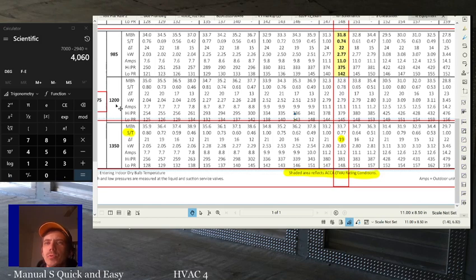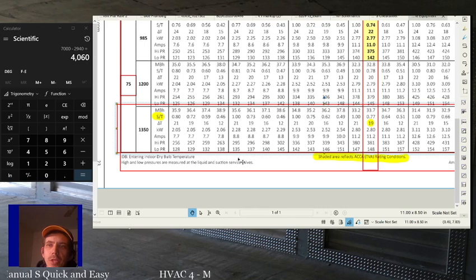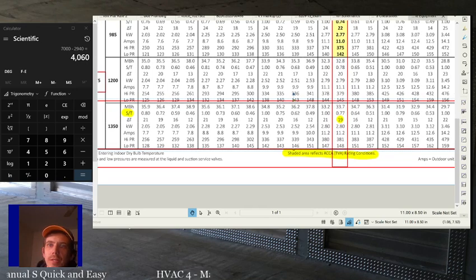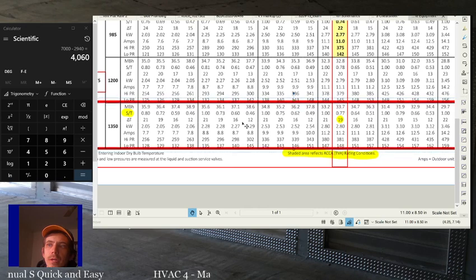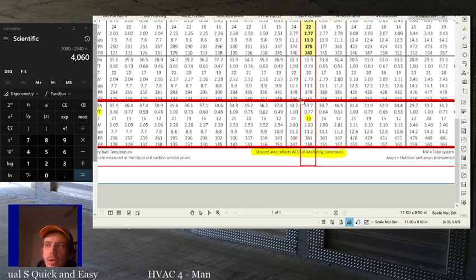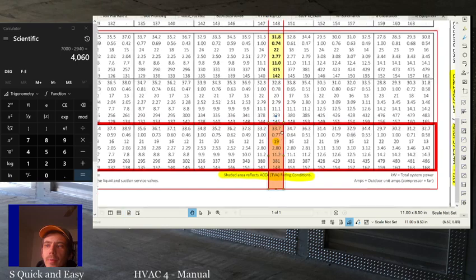Now, 1200 CFM is still within 10% of our target. So we could go 1200 CFM, but for the purposes of this example, we're going to pick the one that's closest and go with 1350. All right, so now we are in this row and this column. So we are right here. This right here is where we're gonna pick our equipment.